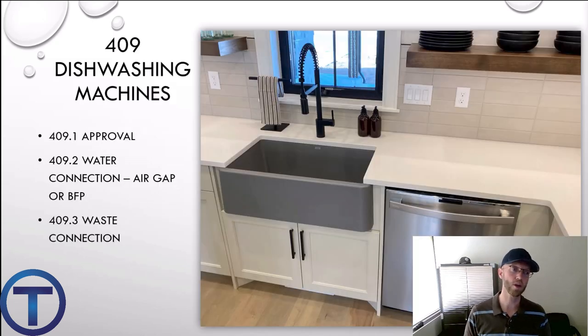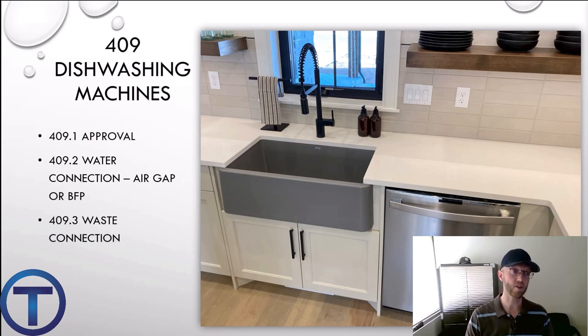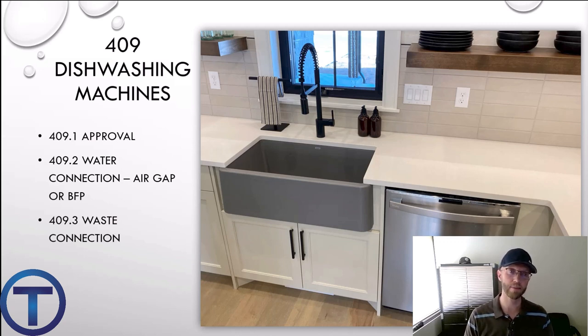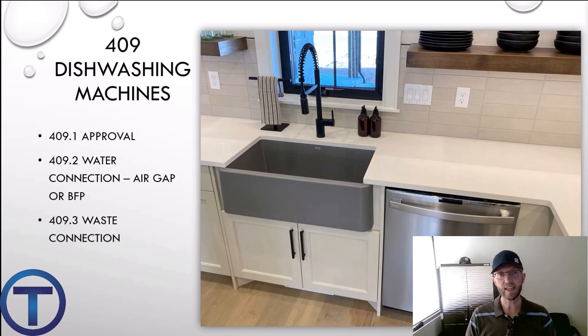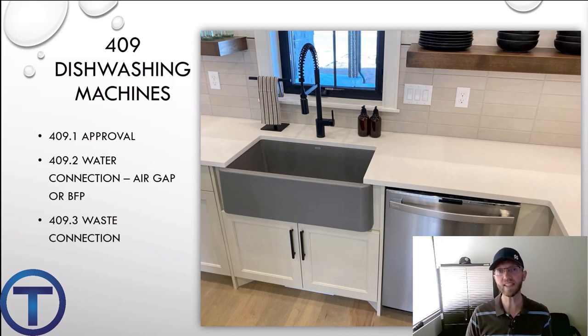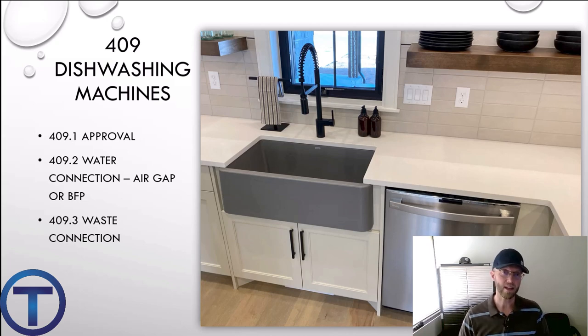In 409, we learn about dishwashing machines. 409.1 covers standards and approvals. 409.2 states that the water connection has to be through an air gap or a backflow preventer — like the washing machine, this air gap is built into the dishwasher. The waste connection can be either an air gap or an air break, and we go into more detail on the waste connection in chapter eight when we look at indirect waste.